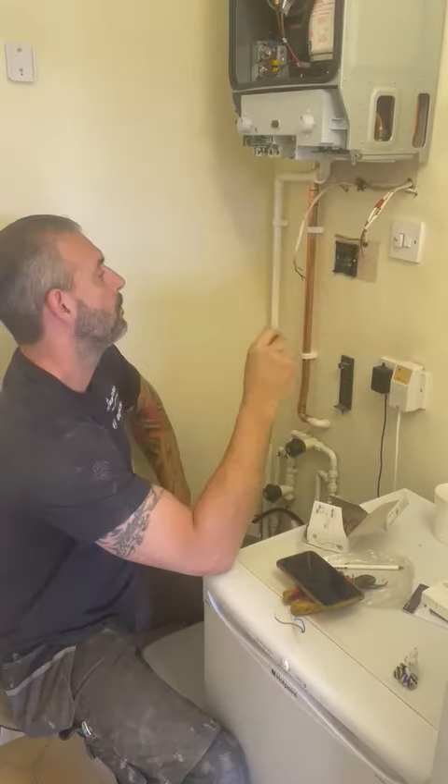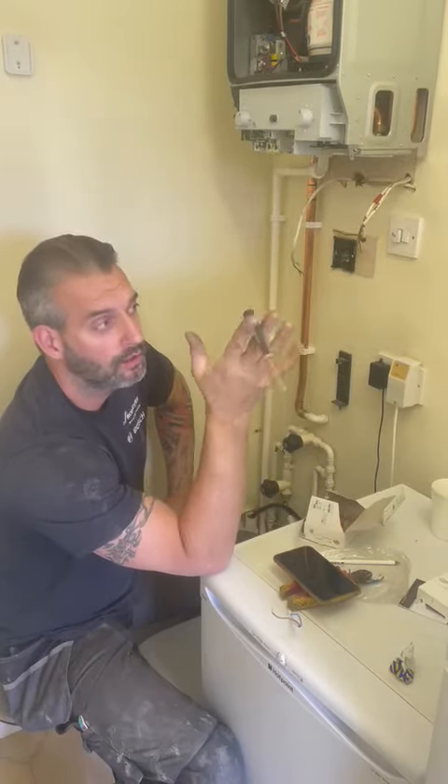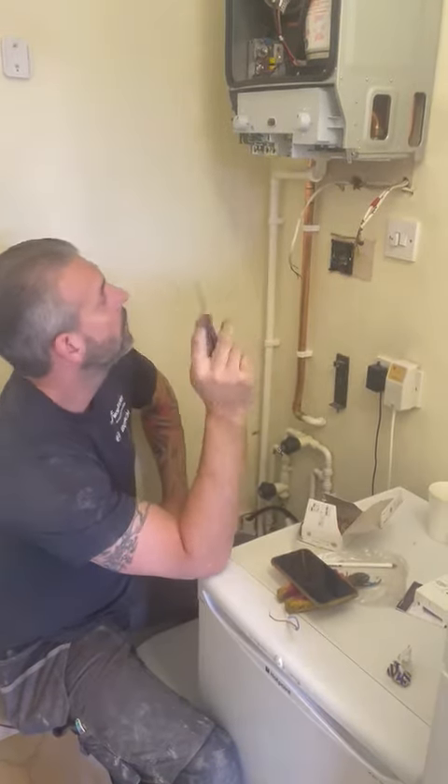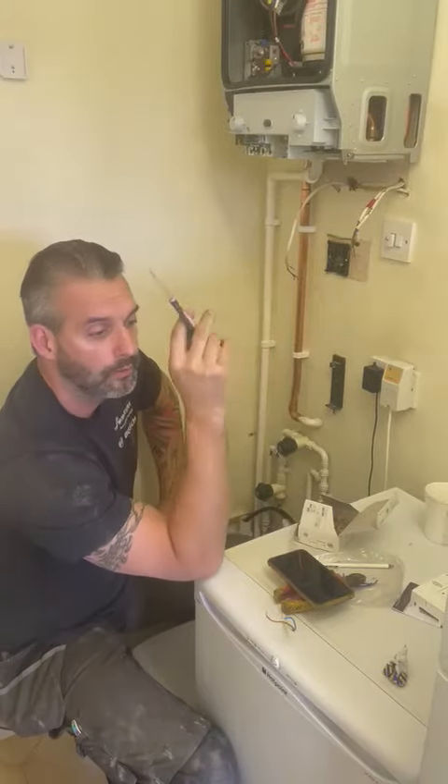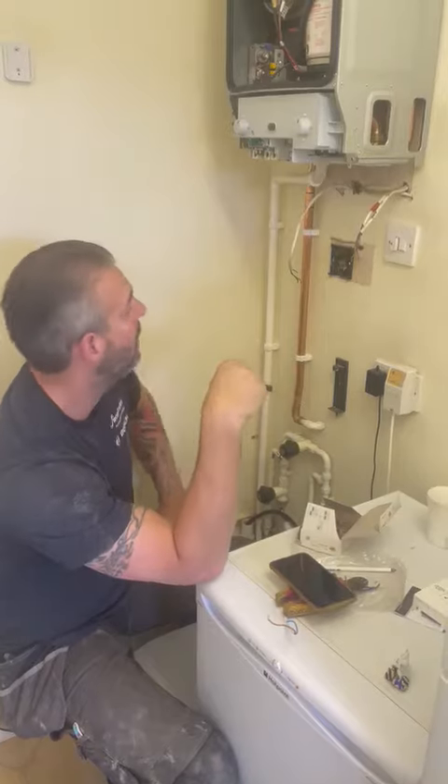It's always good practice. Motorized valves are the most common thing to go wrong on a heating system — moving parts, electrical. Obviously they'll eventually go wrong, so we expect them to last about 20 years on average, so we changed them up.